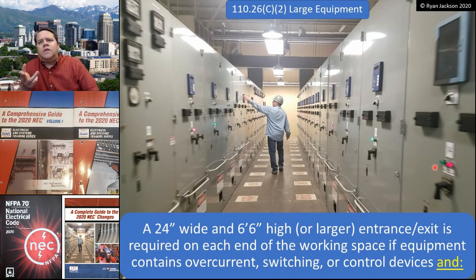So looking at this installation, what we are trying to avoid, let's assume that those pieces of switchgear are pushed up against the end of the wall. So as I run to here, I hit the wall, my nose is touching the wall, I look to my left, there's a switchgear, look to my right, there's a switchgear. That's a violation because I need to have an exit from the working space on each end. Now, all you have to do to comply with this requirement would be to pull those pieces of switchgear back 2 feet away from the wall, and then we would comply.